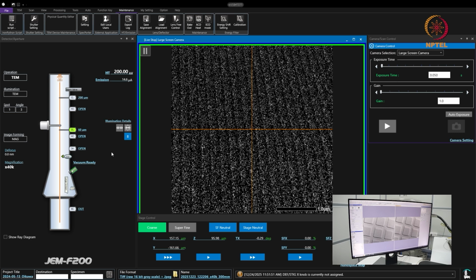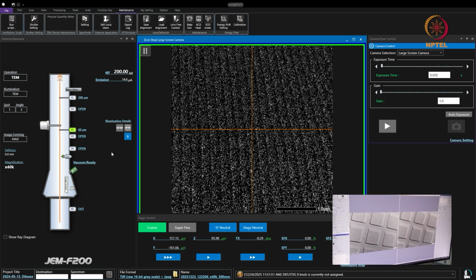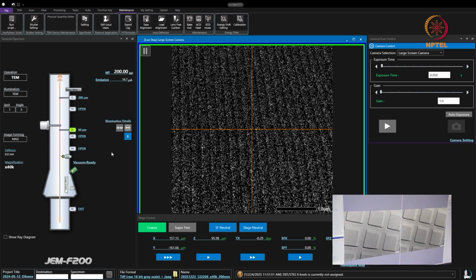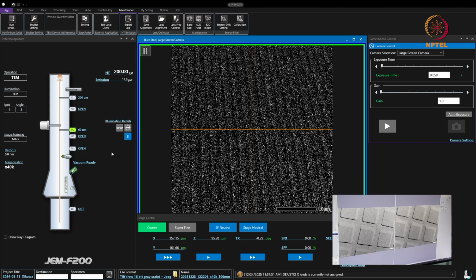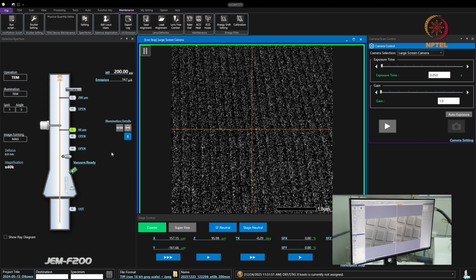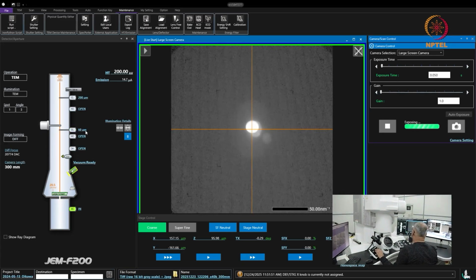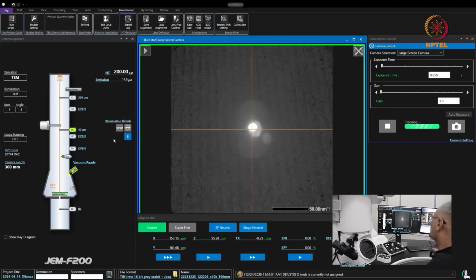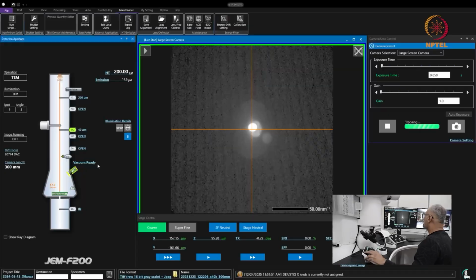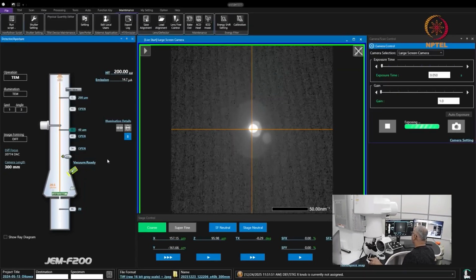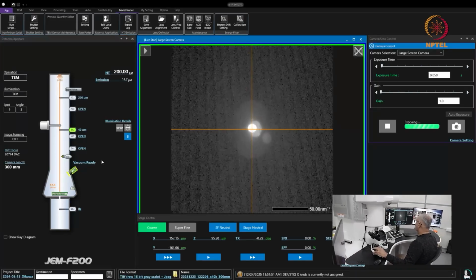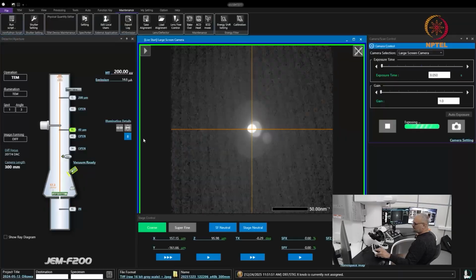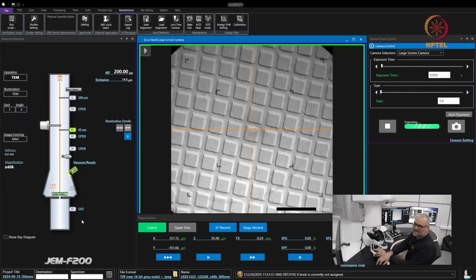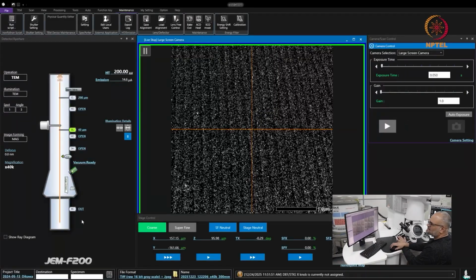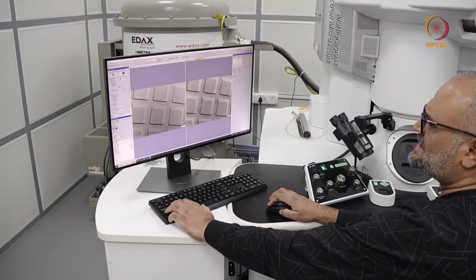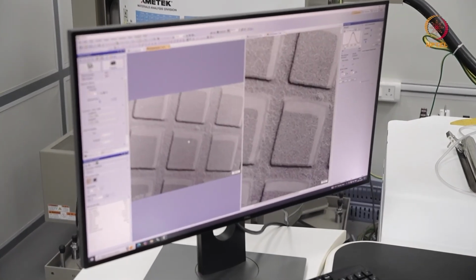Here the image on the right is with the 60 micron aperture in, the image on the left is without any objective aperture in. There is no significant or noticeable improvement in the contrast as yet in a direct comparison. So let me just put in a slightly smaller aperture and then show you how the image quality improves. I'm ensuring that the objective aperture is alright.